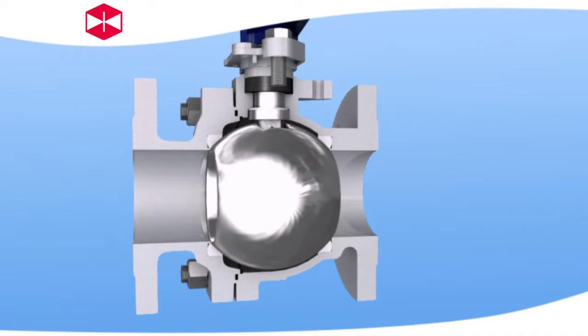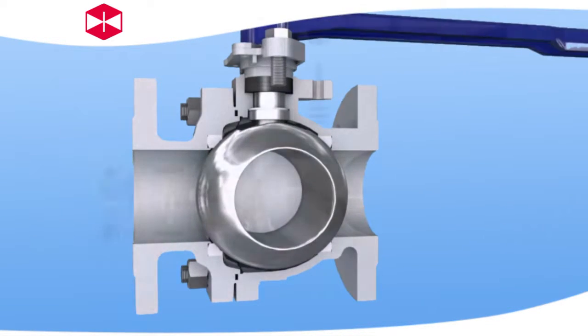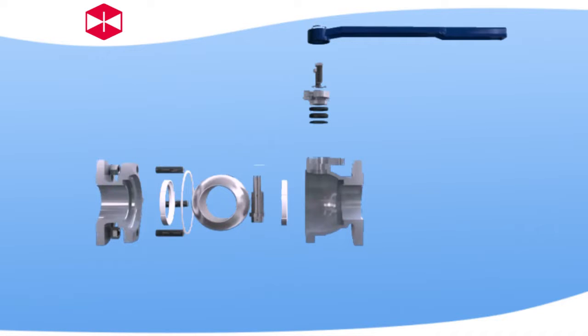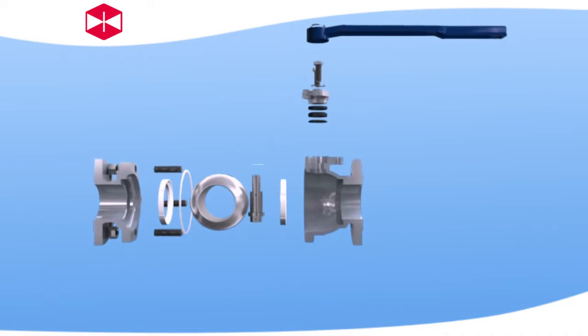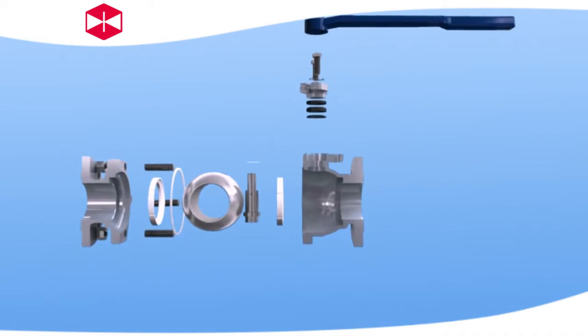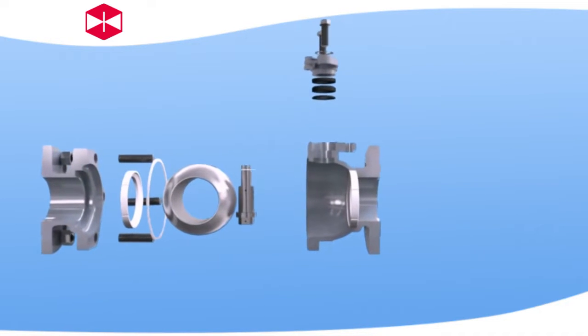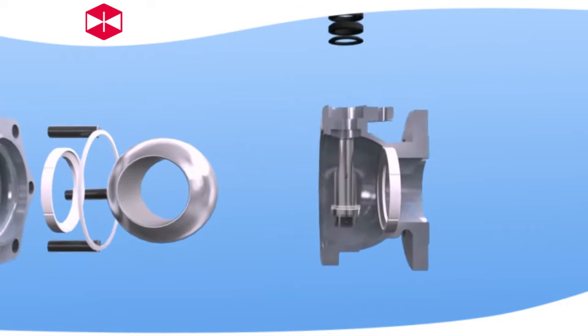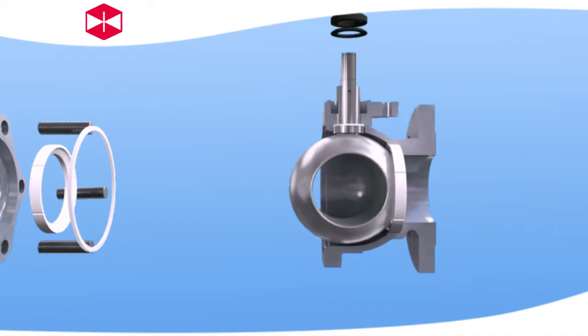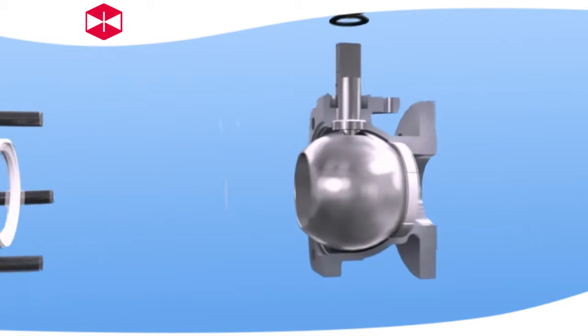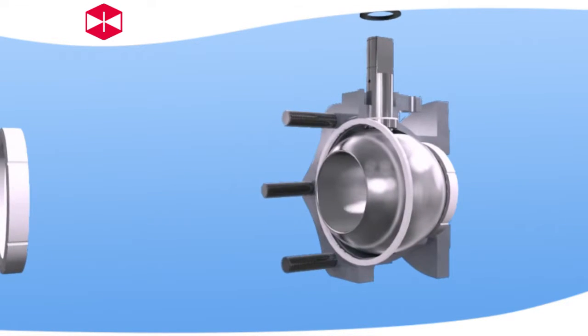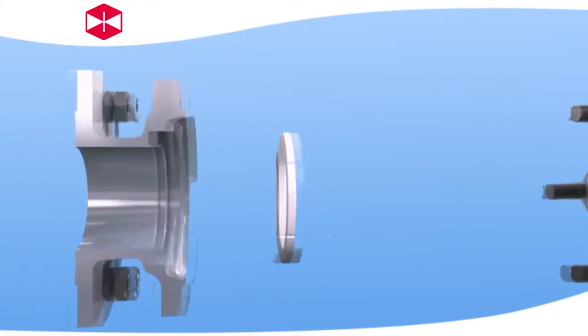When the valve is open, the ball holes line up with the pipeline, ensuring the minimum flow resistance of the pipeline. When the stem rotates up to 90 degrees, the ball hole is vertical to the valve channel, making the ball closely impacted into the seat ring on the exit end by medium pressure, which ensures the good sealing of the valve.